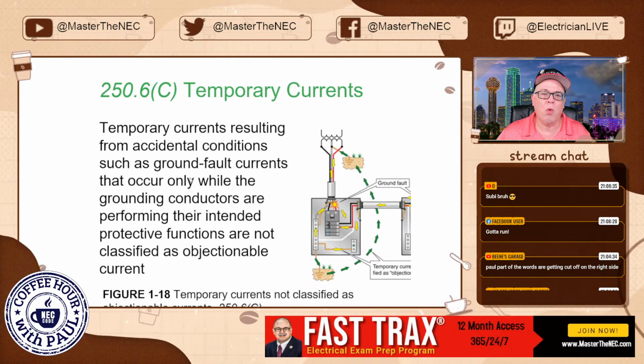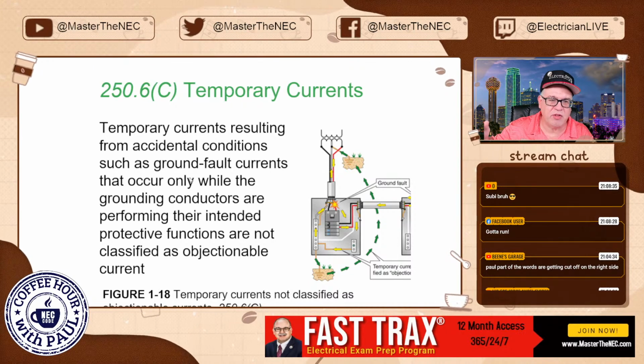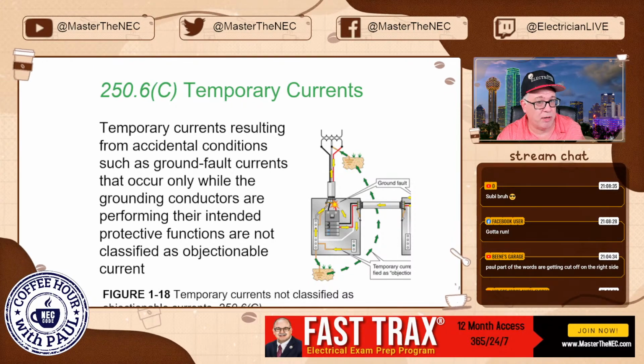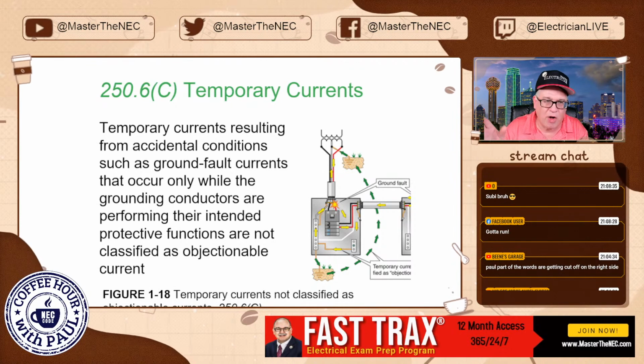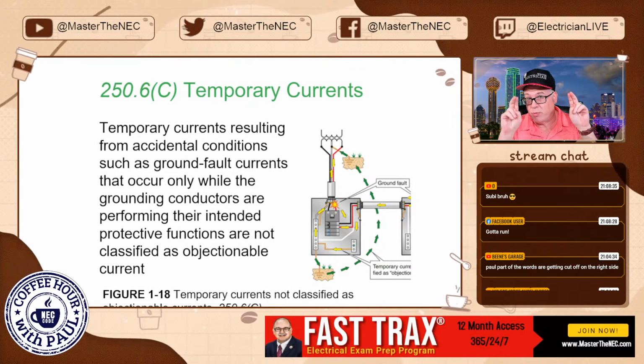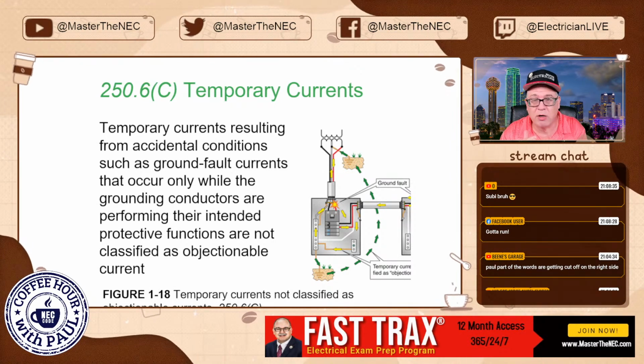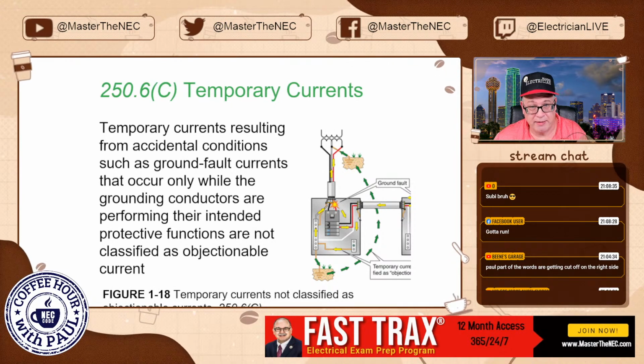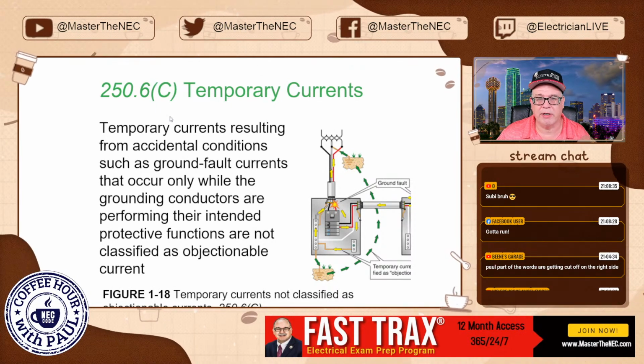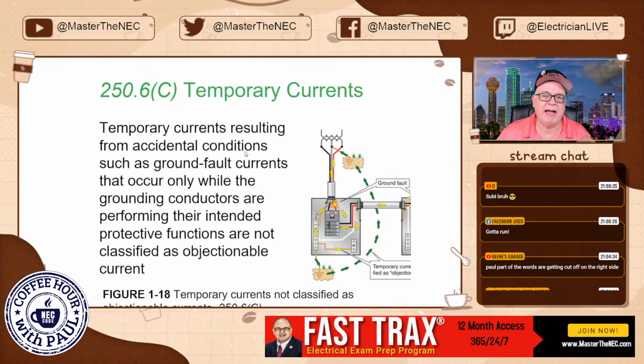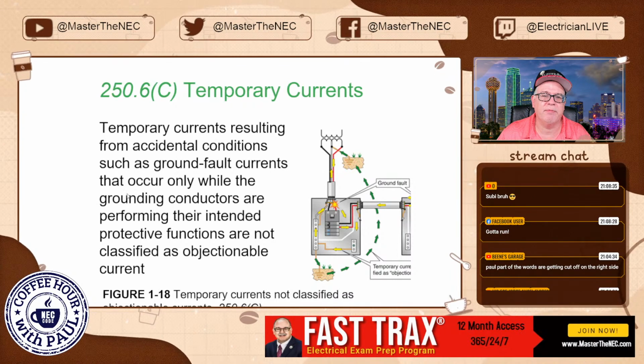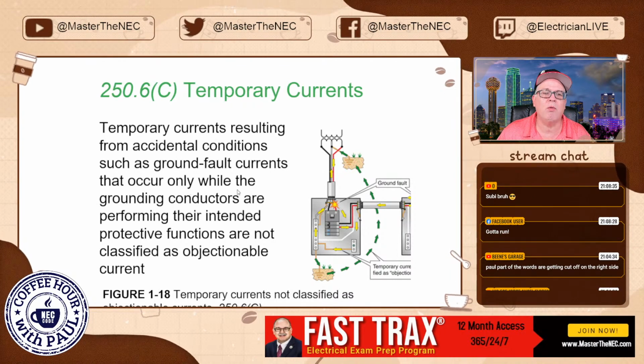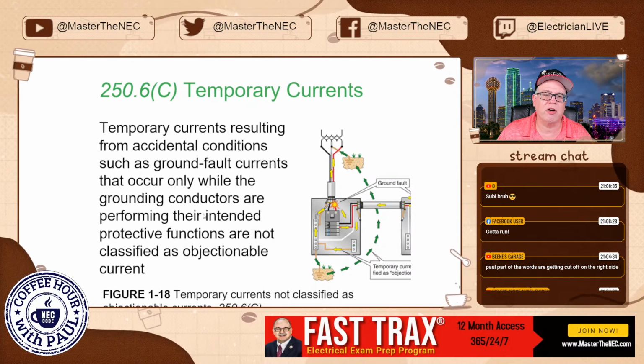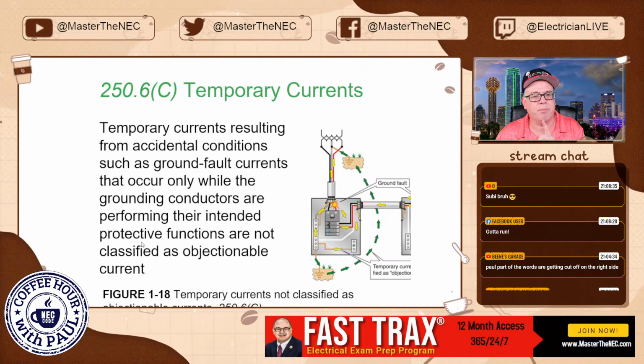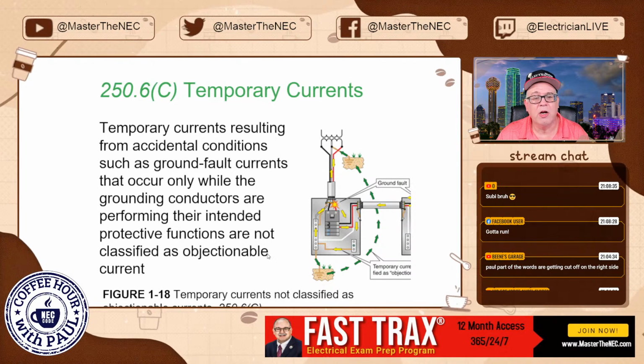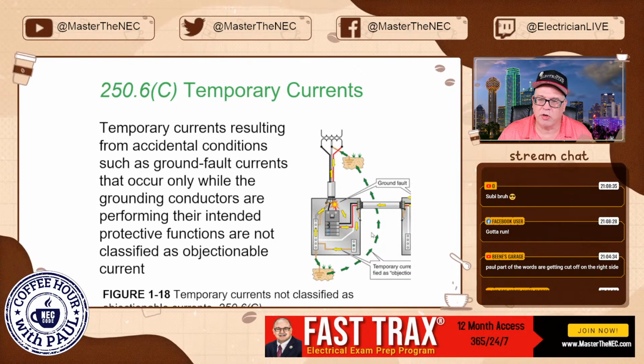Okay? So you don't want to classify those as objectionable current. We have a hard enough time tackling objectionable current than thinking all these possible fault conditions could be considered objectionable current. They're not. They happen very quickly, and hopefully, if you've done everything right, it'll clear the breaker. So temporary currents resulting from accidental conditions such as a ground fault current that occur only while the grounding conductors are performing their intended protective function to clear a breaker are not classified as objectionable current. So here you go right here.